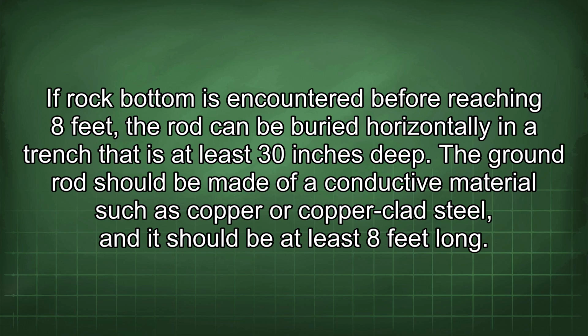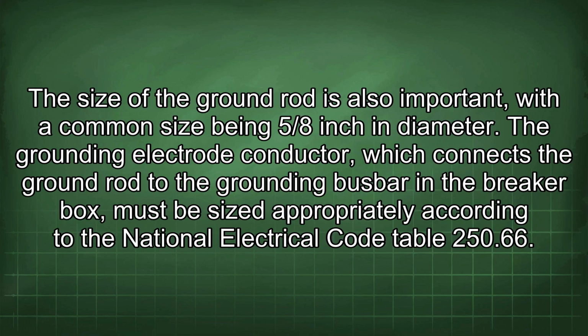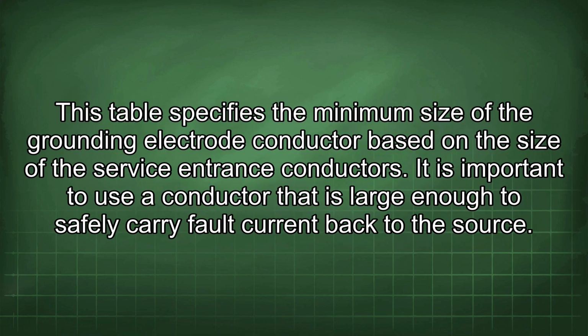The ground rod should be made of a conductive material such as copper or copper-clad steel, and it should be at least 8 feet long. The size of the ground rod is also important, with a common size being 5/8 inch in diameter. The grounding electrode conductor, which connects the ground rod to the grounding busbar in the breaker box, must be sized appropriately according to the National Electrical Code Table 250.66. This table specifies the minimum size of the grounding electrode conductor based on the size of the service entrance conductors.